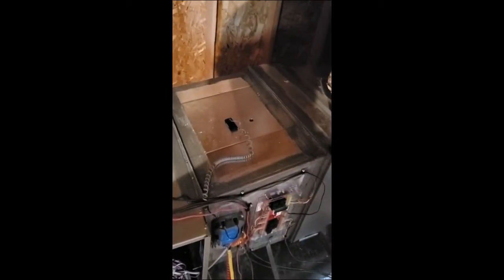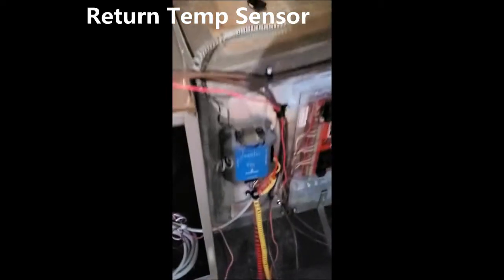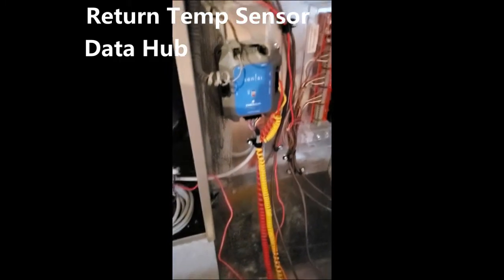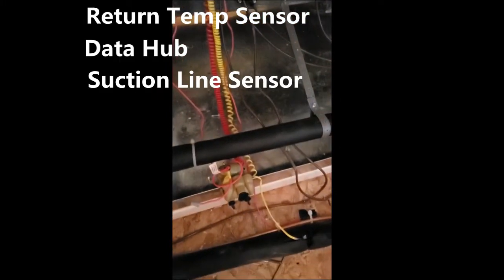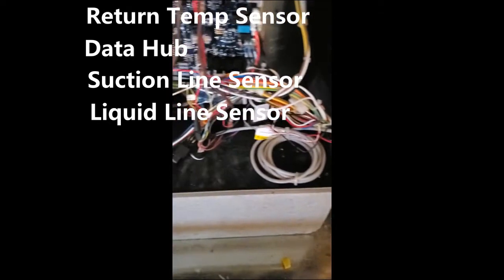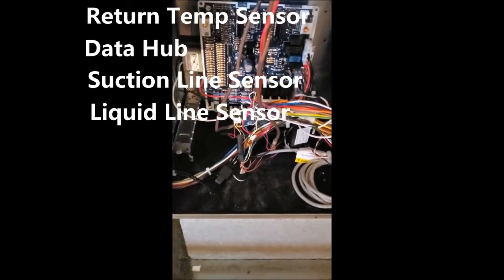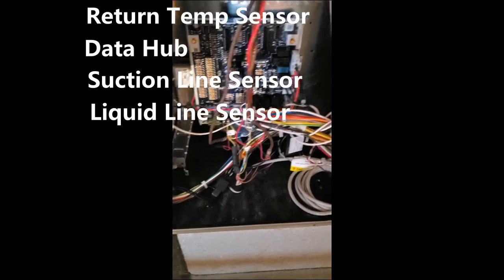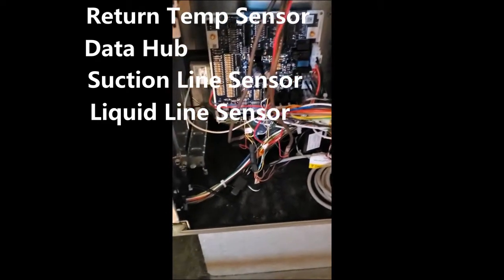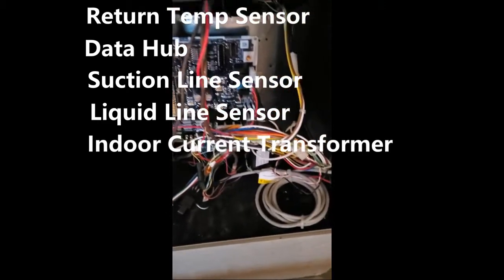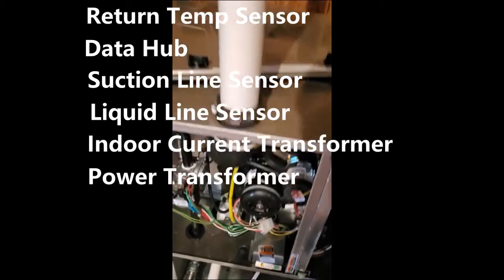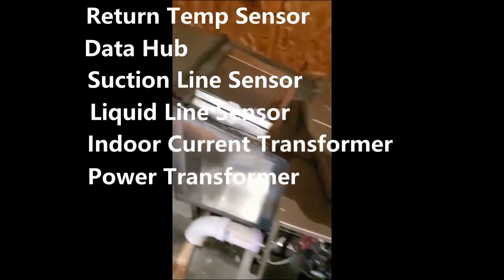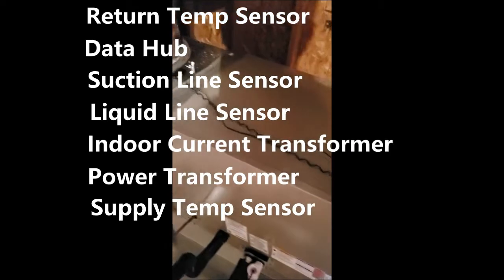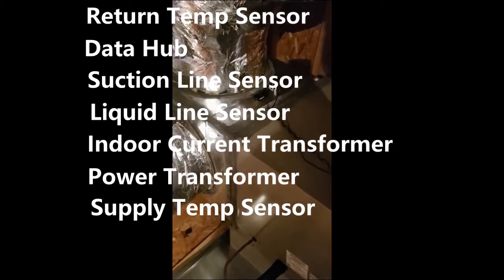So here's everything hooked up. Got your return sensor, your data hub, suction and liquid line sensors. Got all your cables, your connections that monitor what your thermostat, or in this case the zone module, is calling. Got a current transformer, have an isolation power transformer, and then as we continue over here, your supply sensor. We're going to go outside and hook up the outdoor stuff now.